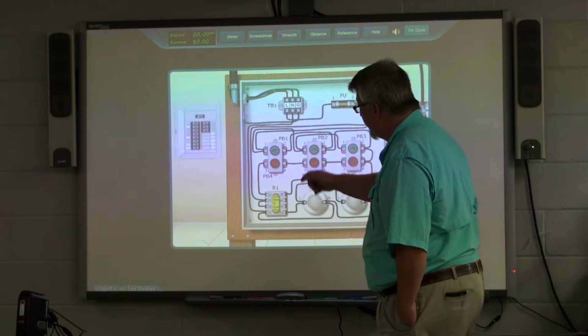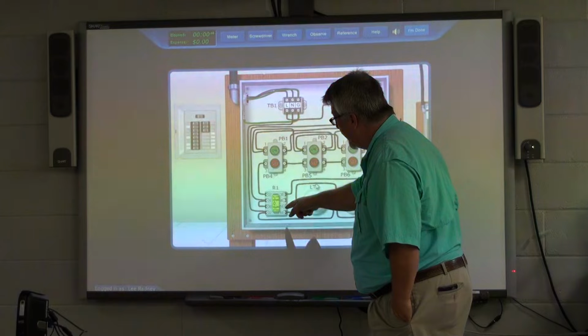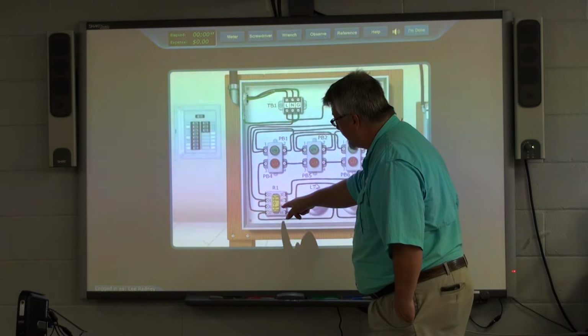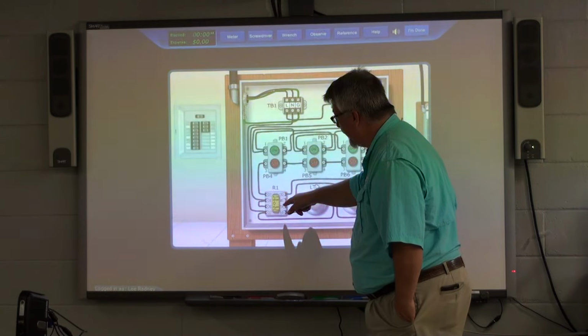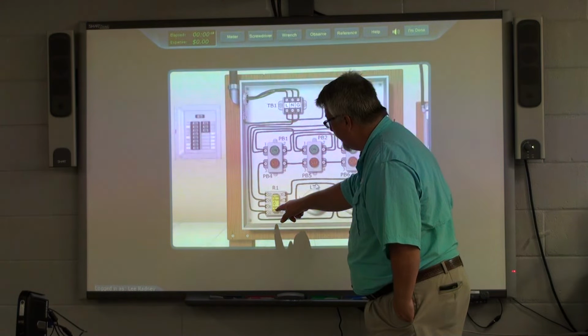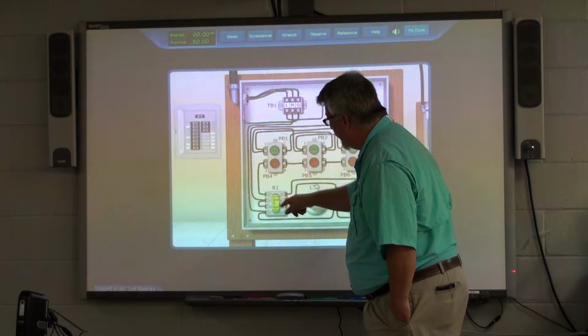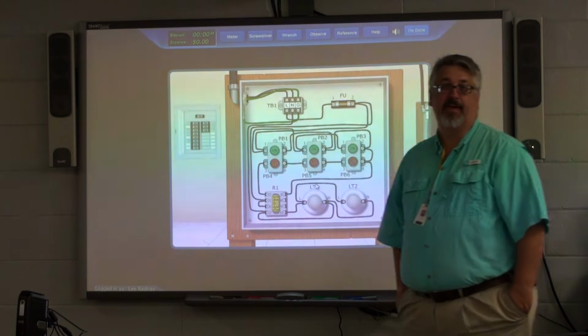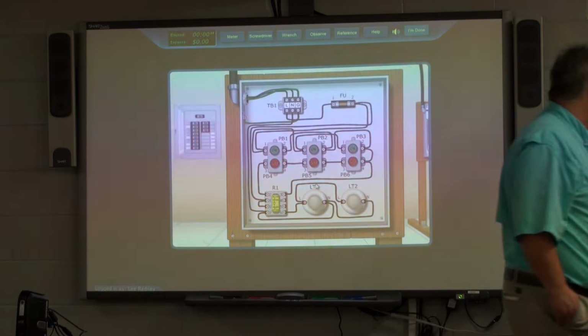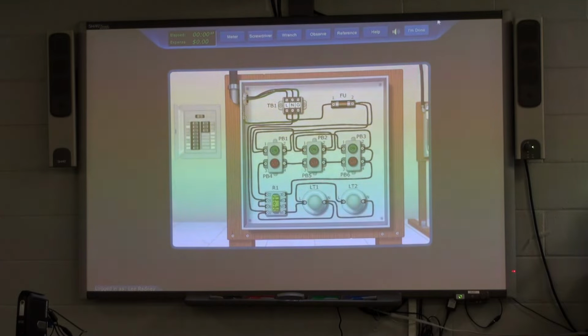And if you look on this relay, it's a little hard to see, but we see pins 5 and 6 are our normally open and normally closed contacts, as are pins 3 and 4. Pins 2 and 7 are our coil, and 1 and 8 are our commons for that relay. The reference doesn't show that, but anyway, we can see our relay.